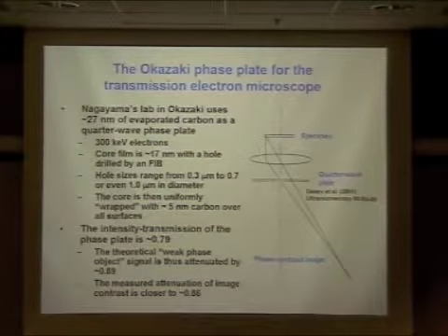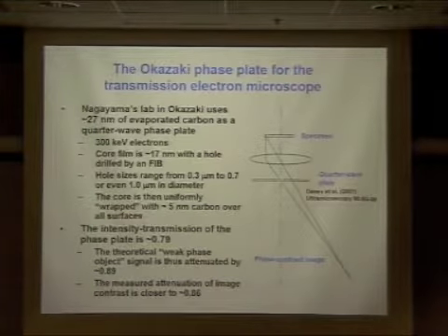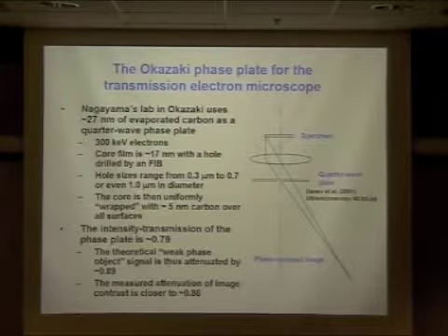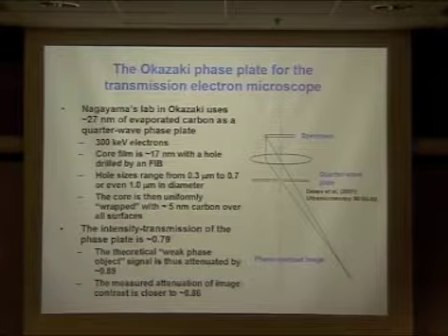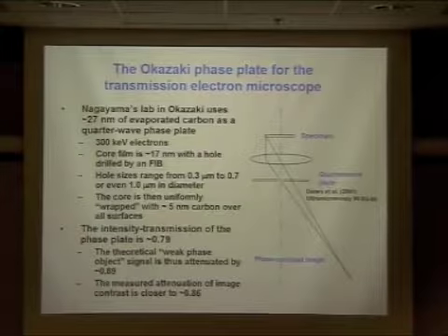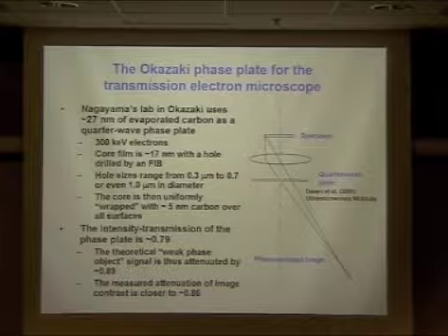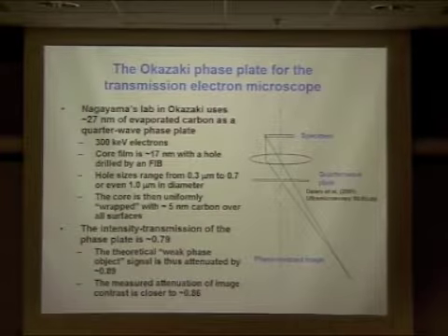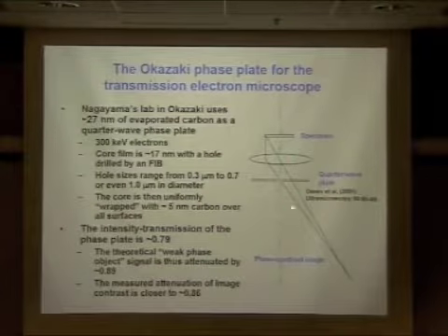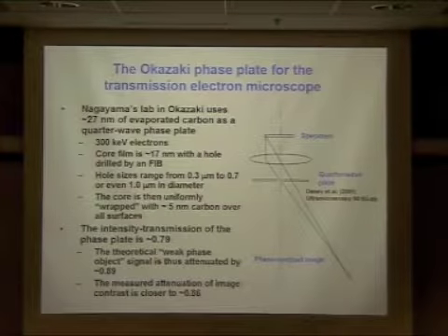There's a published paper, for example, this year, showing that for data collected with a CCD camera at 300 kV and not terribly high magnification, you get identical 3D reconstructions with and without the phase plate at about 12 angstrom resolution. I personally looked at the situation a little bit more, and from estimates of how many electrons would be lost due to scattering, it actually didn't look so bad.